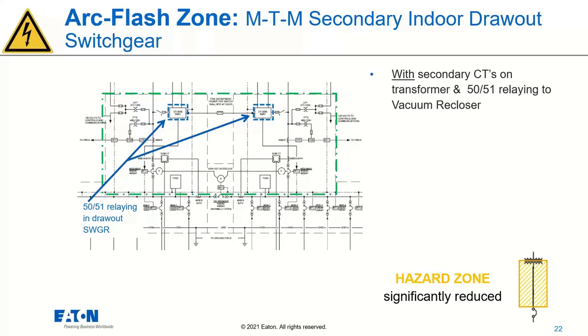And remember, before I show our arc flash values here, why is that vacuum recloser less fast? Why is the primary set of CTs worse than the secondary set of CTs? The real answer is that those primary CTs, the primary always on settings, have to be coordinated for that transformer inrush. And there's going to be a little bit of lag between pulling current on the secondary, reflecting through the transformer, and pulling on the primary. That's not completely negligible, but it's fairly quick. But the real lag comes from the fact that this primary recloser has to be set very far out, very loosely, in order to overcome that transformer inrush. And because it's set loosely like that, it's going to react a heck of a lot slower, and that's going to result in that higher energy.